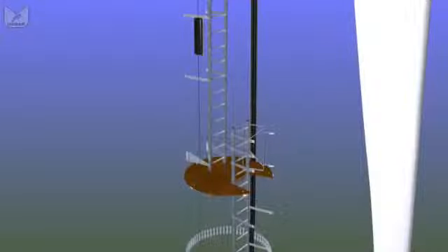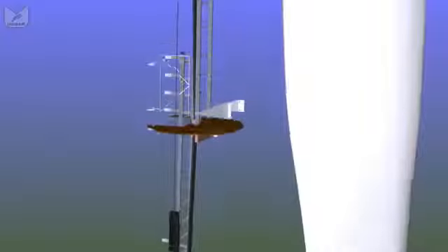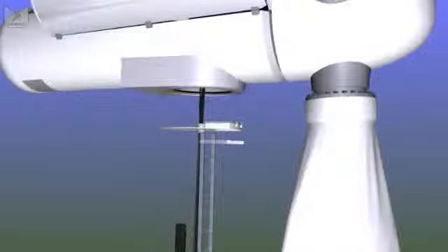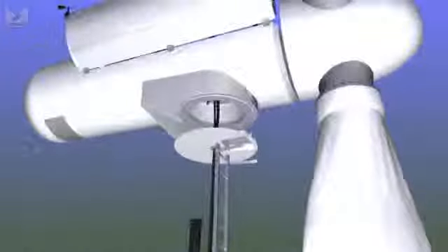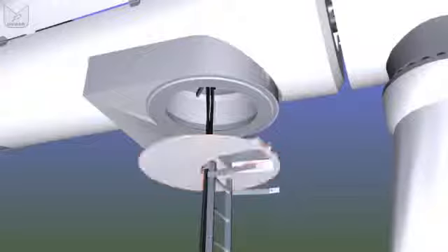But eventually the main cables stop being attached to the wall and they hang freely in the center of the tower, so they can twist as the nacelle rotates to face the wind. If they twist too many times, the nacelle will spin itself around to remove the twists. As we move up, now the cable goes through a hole in the center of each platform, and at the top of the tower we have a steel platform with a sealed trapdoor, which we call the yaw platform. Just above that we have the yaw ring with the bearings that allow the nacelle and the rotors to rotate around to face the wind.